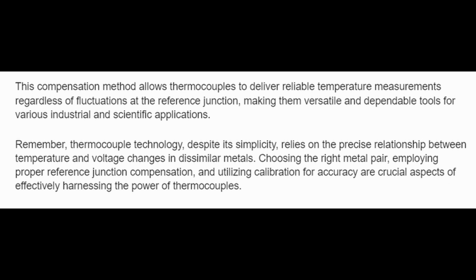This compensation method allows thermocouples to deliver reliable temperature measurements regardless of fluctuations at the reference junction, making them versatile and dependable tools for various industrial, scientific, and marine applications. Remember, thermocouple technology, despite its simplicity, relies on the precise relationship between temperature and voltage changes in dissimilar metals. Choosing the right metal pair, employing proper reference junction compensation, and utilizing calibration for accuracy are crucial aspects of effectively harnessing the power of thermocouples.